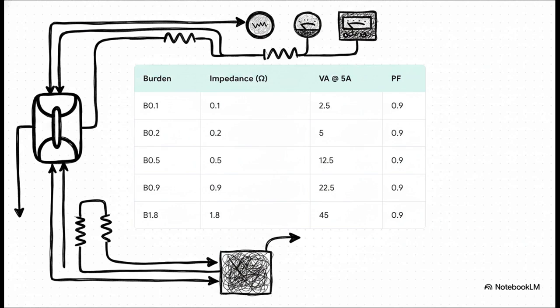Take a look at this standard IEEE burdens data. Now, the term burden might sound complex, but it's really just the load connected to the CT secondary expressed in ohms. All this data just represents standard ohm values from B0.1 all the way up to B1.8. Basically, it represents the total combined resistance of your devices and all your connecting lead wires.